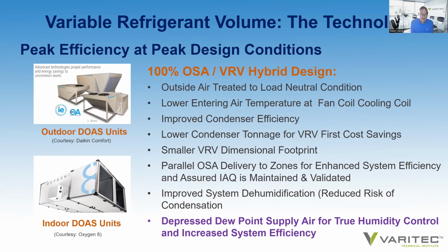So a parallel outside air delivery to zones for enhanced system efficiency and assured IAQ is maintained and validated. You can actually regulate the amount of outside air a building owner wants to the space, whether it be code minimum as prescribed by ASHRAE Standard 62.1, or increase the air change rates with outside air to reduce the risk of infection even further, as ASHRAE's Epidemic Task Force guidelines recommend. And you can add another layer of improved IEQ with deeper humidity control. And we're going to demonstrate that here shortly.